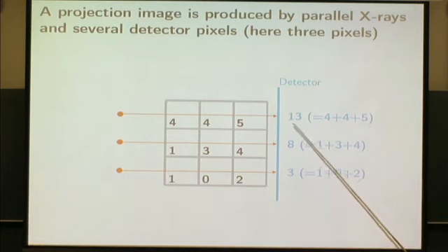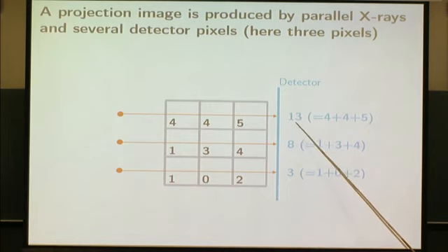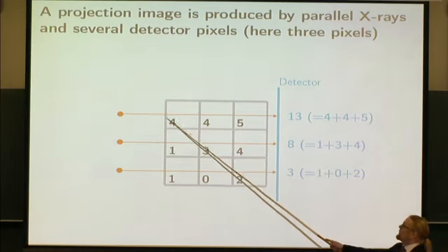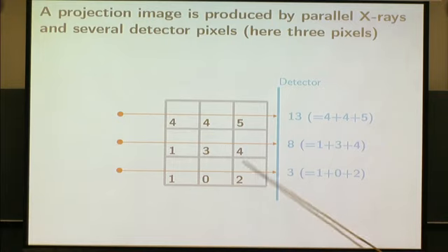So after calibration, we can interpret the numbers coming from the detector. Actually, the photon counts, we take a logarithm and subtract from the maximum. After that, we have something proportional to these numbers, which in this case are kind of length of this path inside times the attenuation. So we get row sum of this small pixel image.